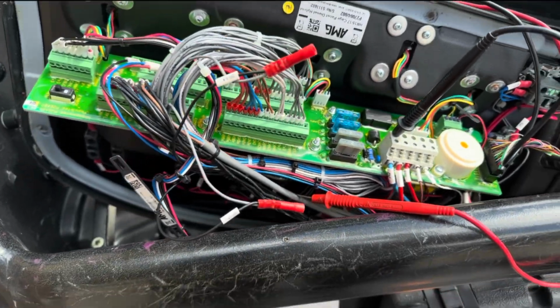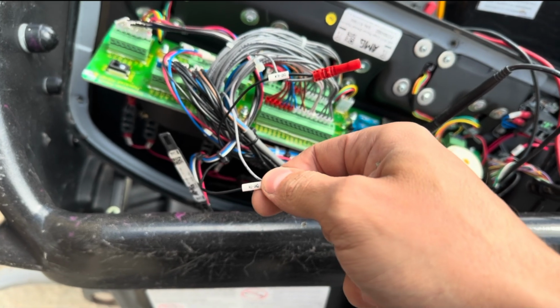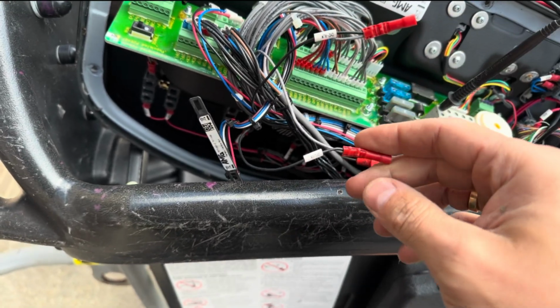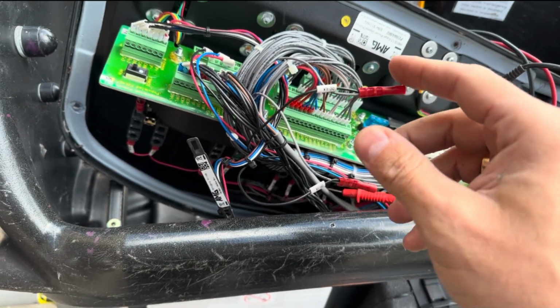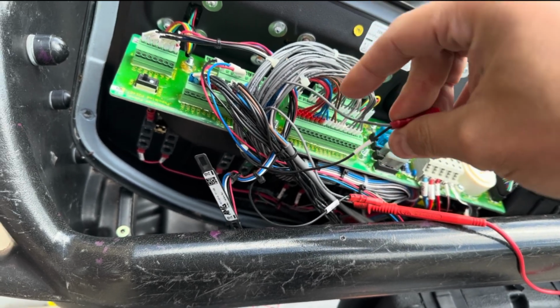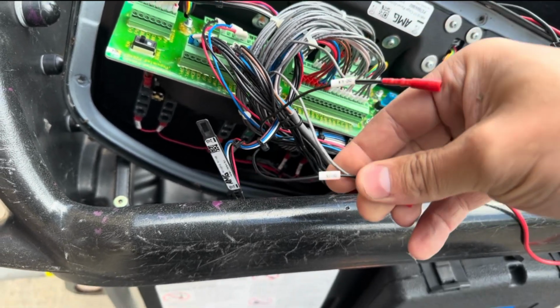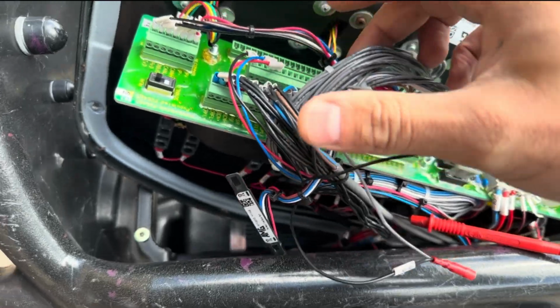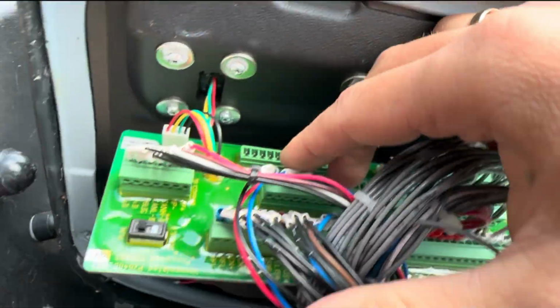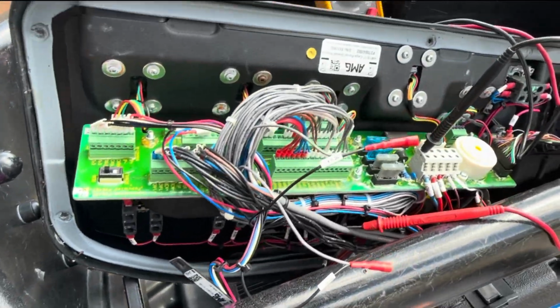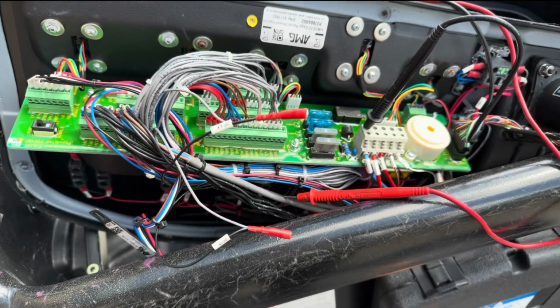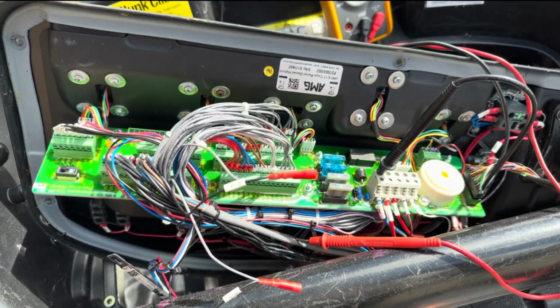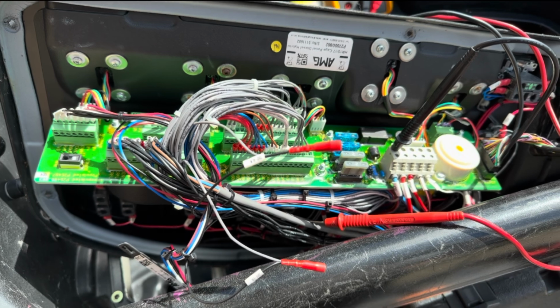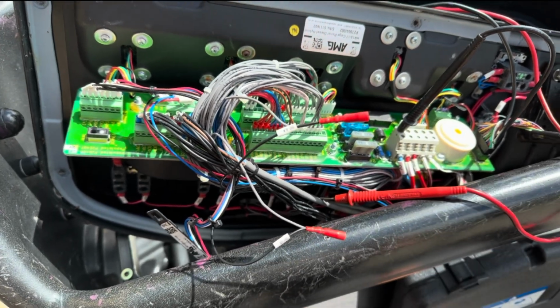So inside the console now, there are two connections here, channel 1, channel 2. Both channels are from the load cell, so they connect directly to the PLC. This gray wire goes to the PLC, and this connector here is the power supply to the cell. So I don't think it's an issue with the power supply, as the cell is producing output on one channel. So we have to look to see what sort of voltage we're getting here.